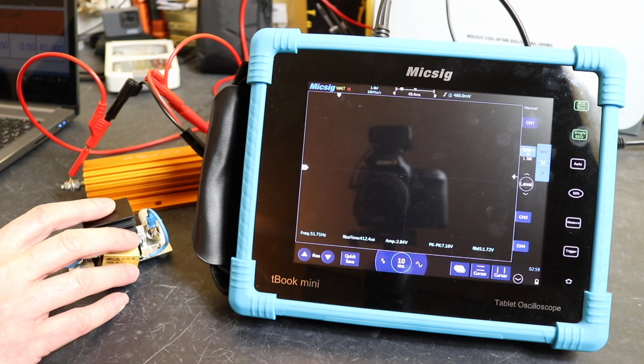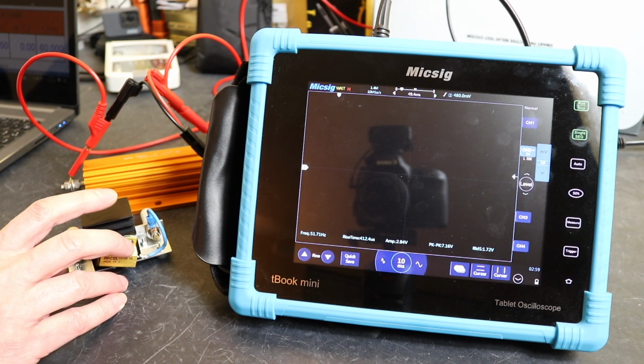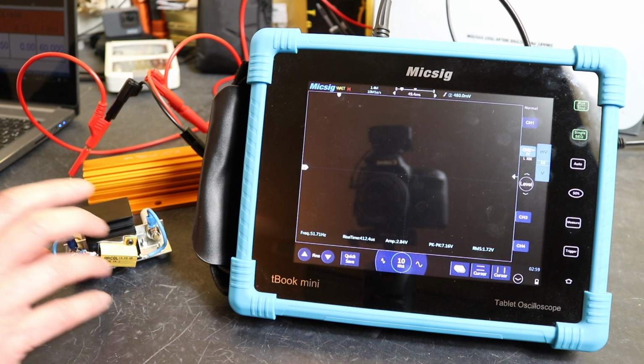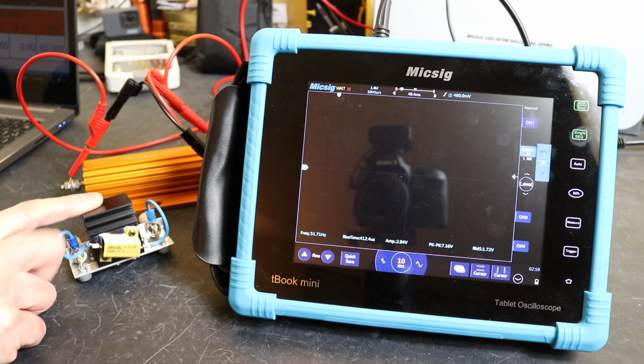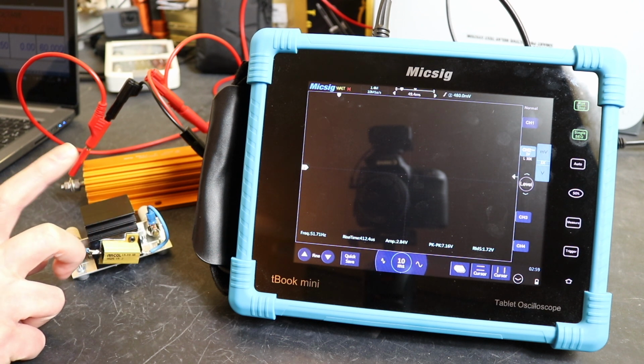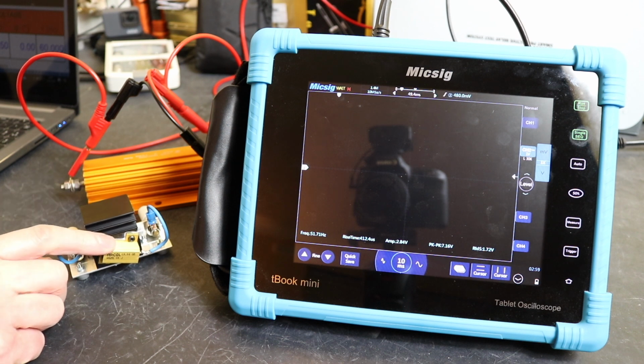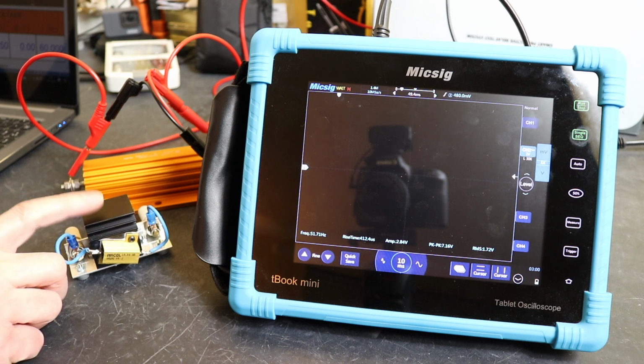These injection test sets, they do have a voltage burden for the current outputs that they are capable of driving. And with a 1 ohm resistor, 6 amps, I will need 6 volts across it. For 20 amps, I will need 20 volts across it. And unfortunately, our SMRT1 cannot deliver that voltage burden.